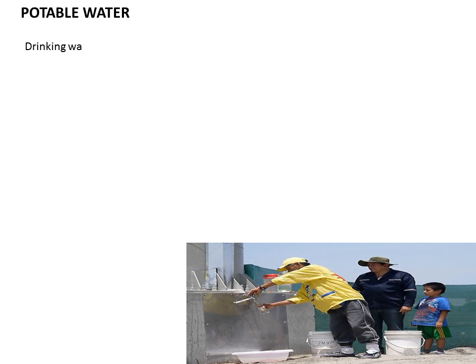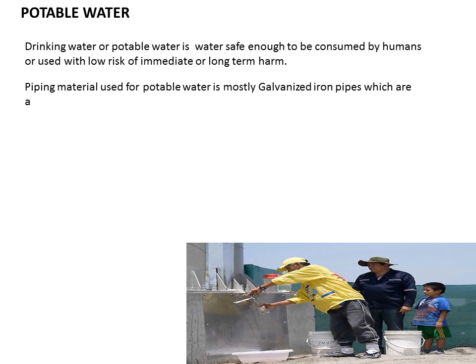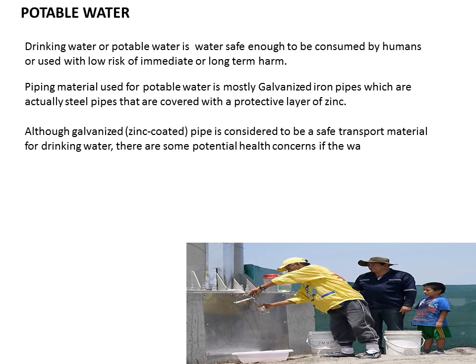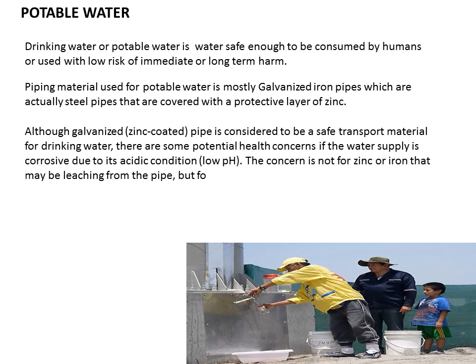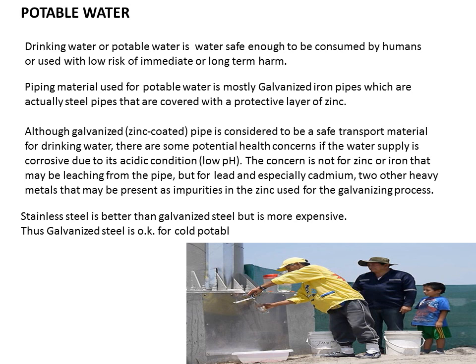Potable Water. Drinking water or potable water is water safe enough to be consumed by humans or used with low risk of immediate or long-term harm. Piping material used for potable water is mostly galvanized pipes — steel pipes coated with a protective layer of zinc. Although galvanized pipe is considered a safe transport material for drinking water, there are potential health concerns if the water supply is corrosive due to acidic (low pH) conditions — specifically the risk of lead and cadmium impurities leaching from the zinc used in galvanizing. Stainless steel is better than galvanized steel but more expensive. Galvanized steel is acceptable for cold potable water.